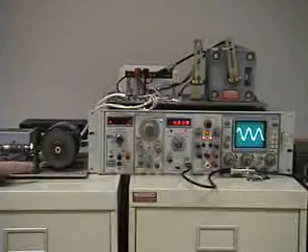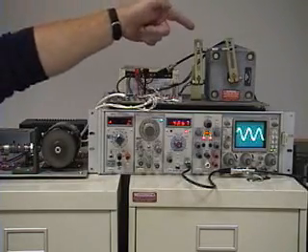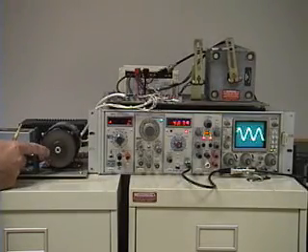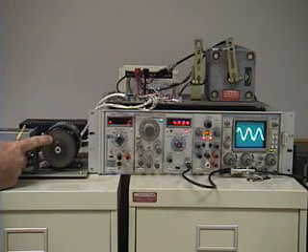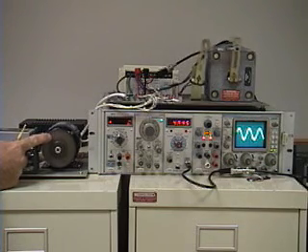As I put some load onto the gear, you'll see the actuator call for more fuel. So just putting a little pressure on there causes the actuator to go to more fuel, and you'll see the PID action bringing the control back into rated speed.